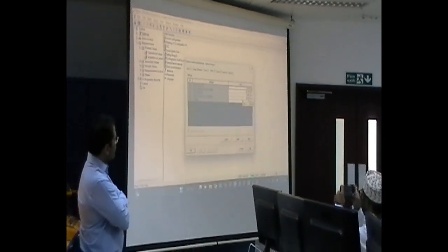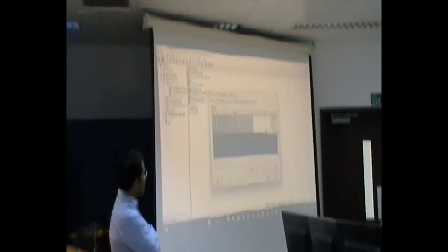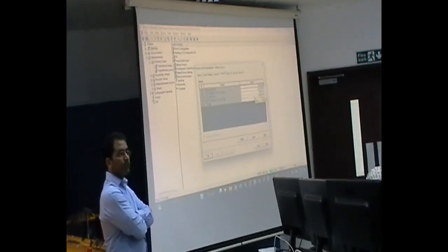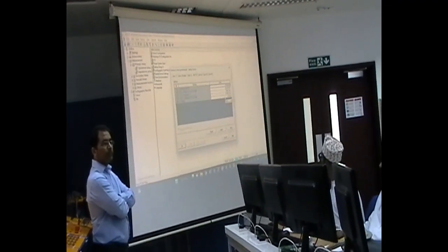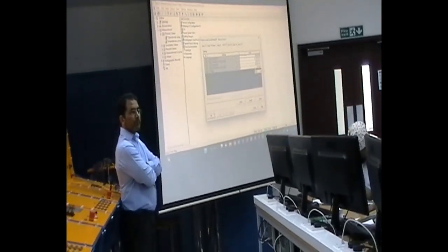Zone 3. Usually zone 3, assuming this relay is in the 33 kV side of the sending end of the line, zone 3 could have reached to cover the 11 kV of the substation. So the impedance here is quite high relatively. But anyhow, for testing purpose, I've reduced it a little bit. So the resistance for phase fault is 22.1. The reactance is 8 ohm. And the resistance for phase to earth is 30.2. And the time? 1 second, 0.2, which is very, very high in terms of protection.